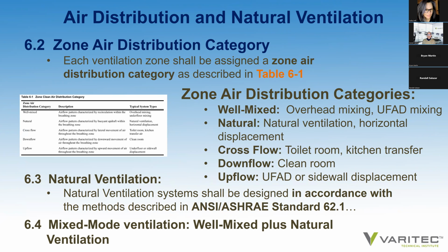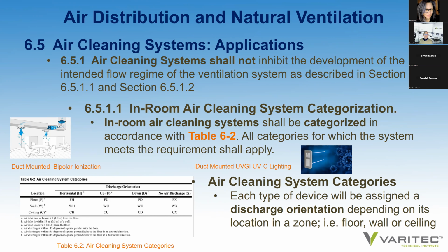So in order to understand the appropriate solution to serve each zone, ASHRAE 241 assigns that each zone shall have an air distribution category. Those categories are comprised of well-mixed environments, natural environments, cross-flow environments, downflow, and upflow. It's rather interesting that horizontal displacement ventilation falls under the category of natural. Section 6.3 also offers some guidance on natural ventilation, and 6.4 on mixed mode ventilation, which is a combination of air handler conditioned air versus natural ventilation in a building. Well, we just don't have time to get into those sections, and nor would they immediately apply, certainly for us in the South, certainly in Phoenix, Arizona, and the Sonoran Desert.